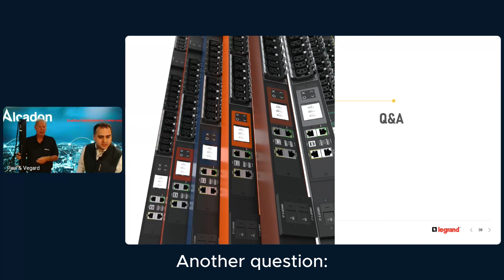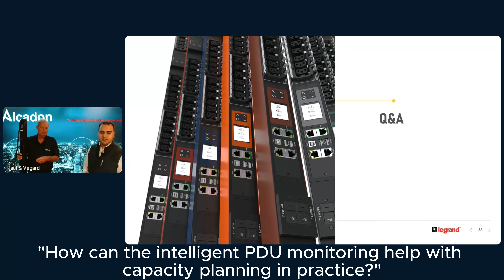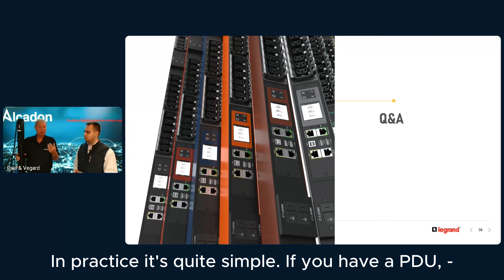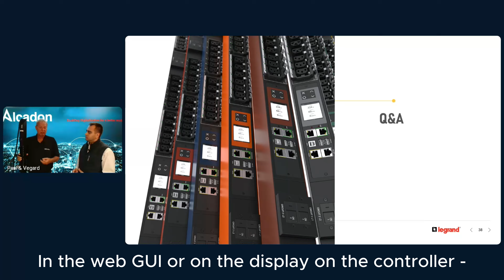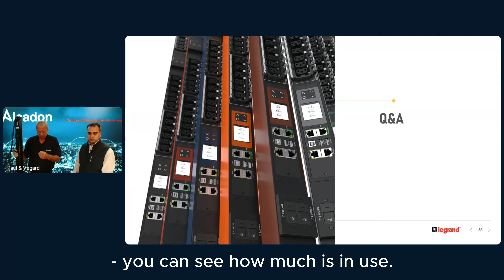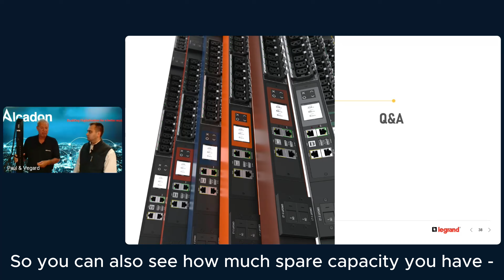Another question: how can intelligent PDU monitoring help with capacity planning in practice? It's quite simple. If you have a PDU, it has a specific capacity. In the web GUI, or on the display on the controller, you can see how much capacity is in use, so you can also see how much spare capacity you have for adding additional servers.